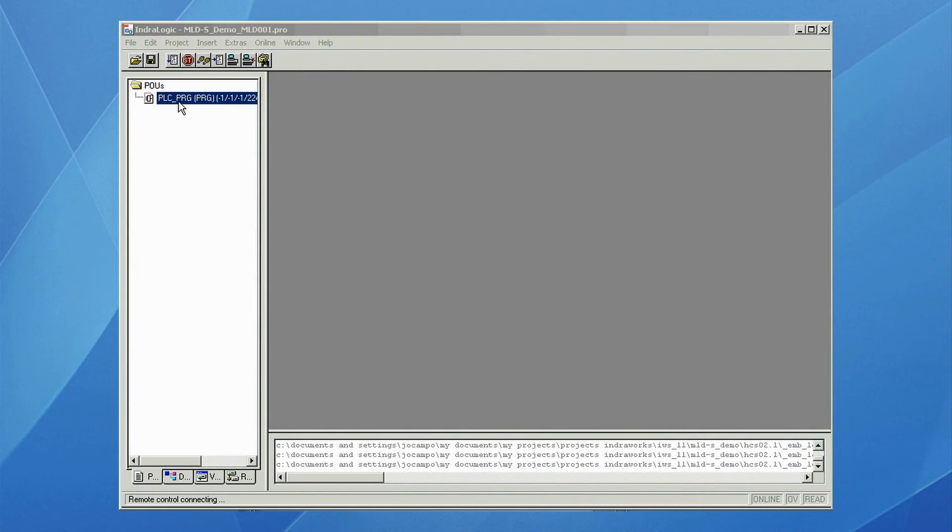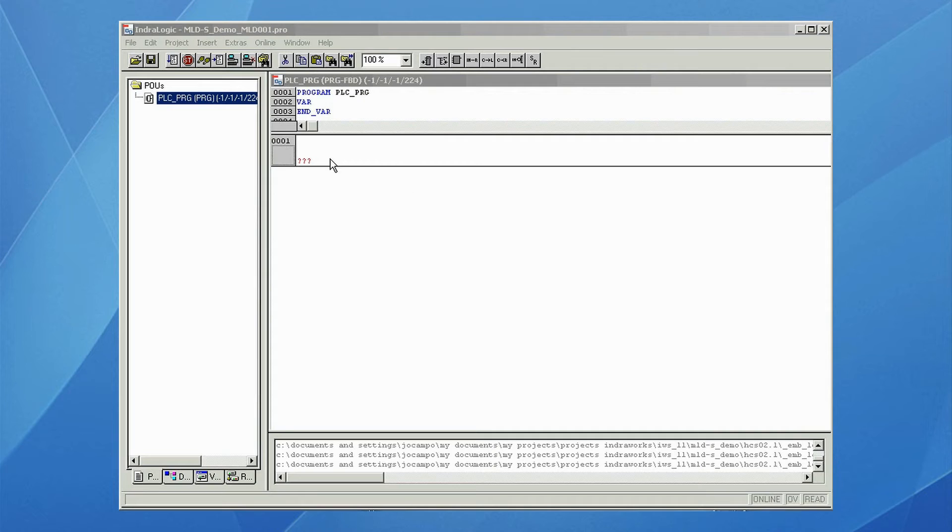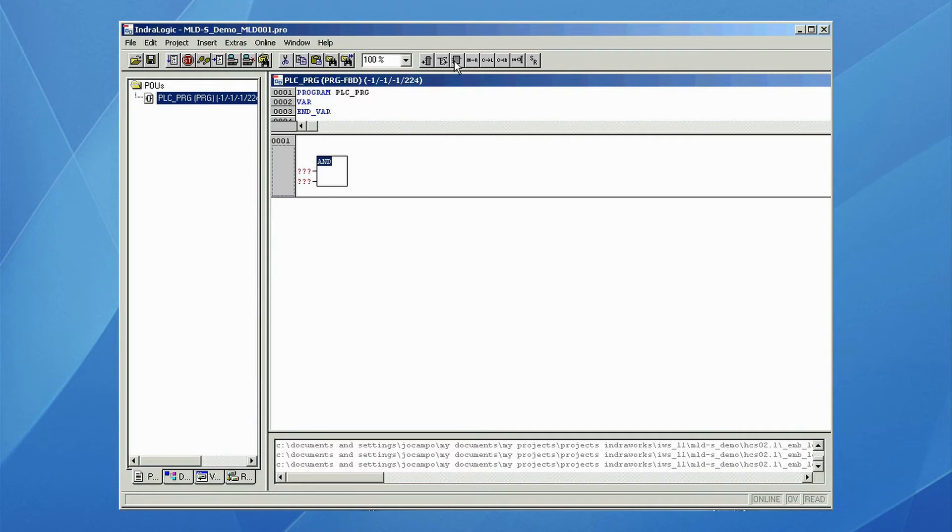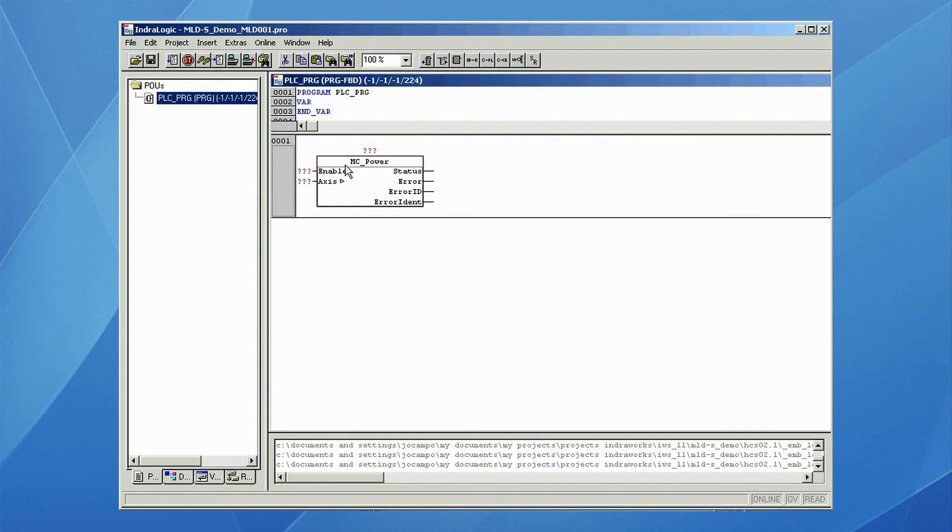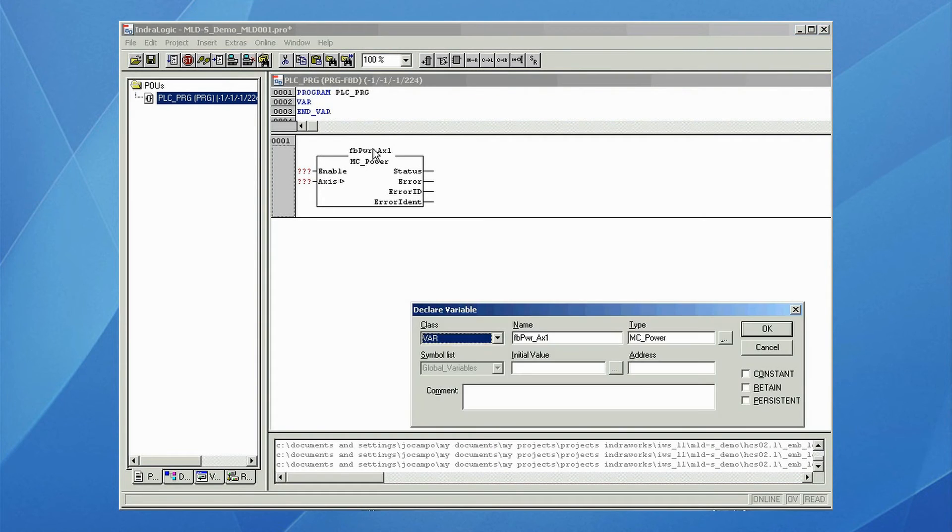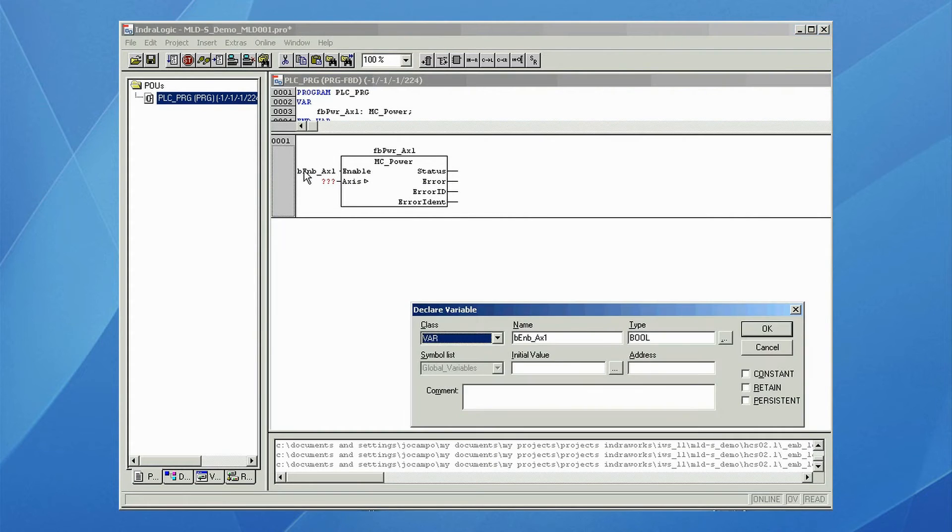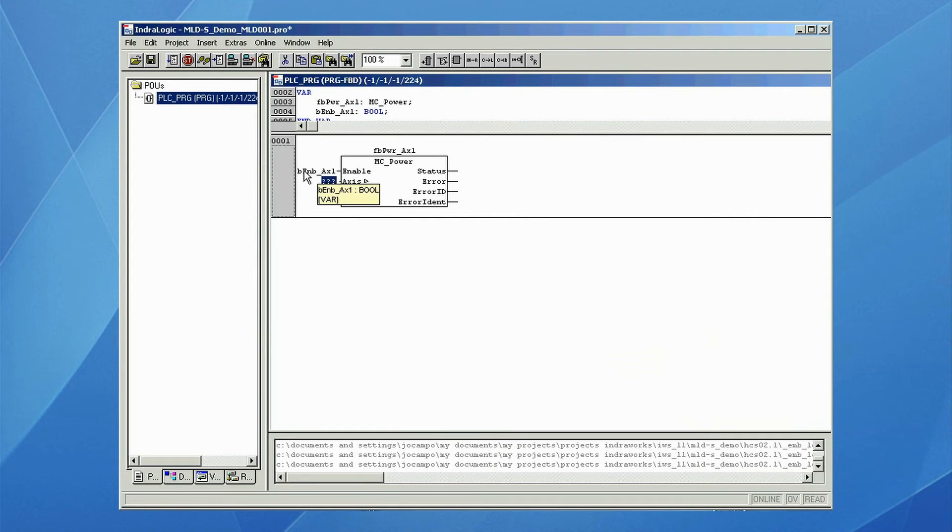In this example, we will enable the drive, move the axis in velocity mode, and stop the axis. We will add the corresponding PLC open motion function blocks. We add MC power function blocks to enable the drive, and we declare the instance of the function block, add the input variable to enable the function block, and add the axis that is going to be enabled.